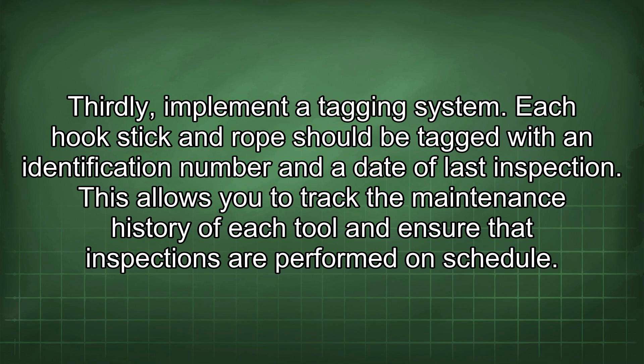Thirdly, implement a tagging system. Each hook, stick, and rope should be tagged with an identification number and a date of last inspection. This allows you to track the maintenance history of each tool and ensure that inspections are performed on schedule. The tag should also include information on the tool's safe working load or maximum operating voltage.